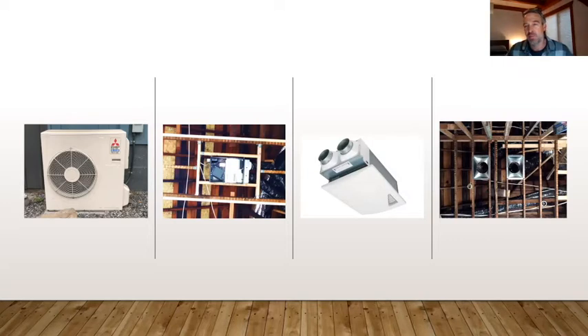Anytime we have something where it might be pushing the limits of what a system can do, it's always good to have that discussion up front and to go through that with the technicians, and they can run the specs. They might go to a larger air handler unit itself. Those air handlers are sized based on the square footage of the space and the number of rooms. And they might size it based on a normal filter, and they might need to go up one size larger in order to compensate for that.